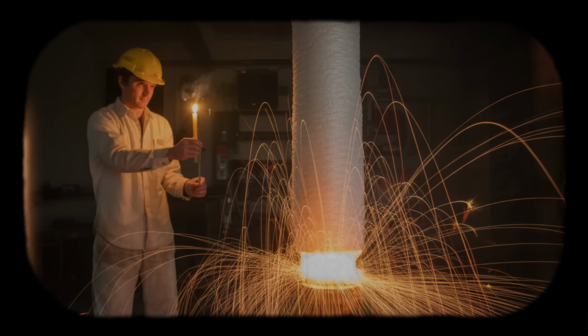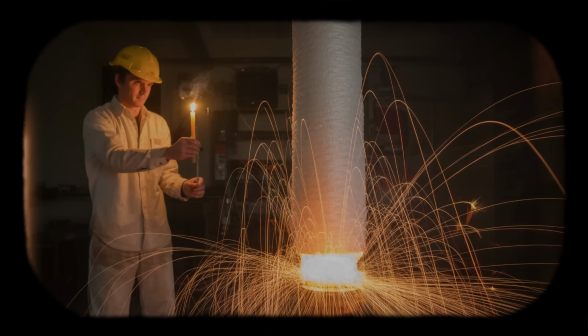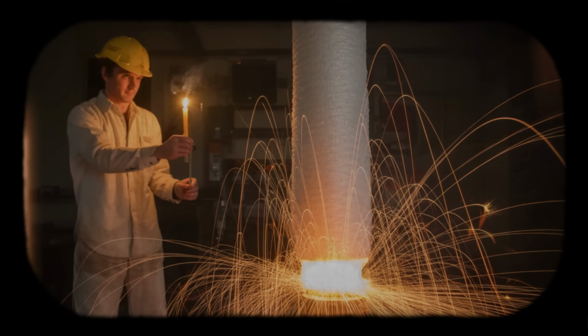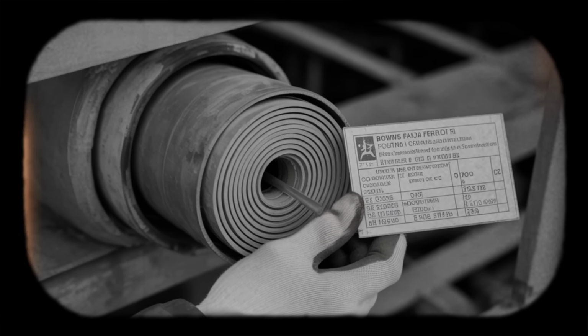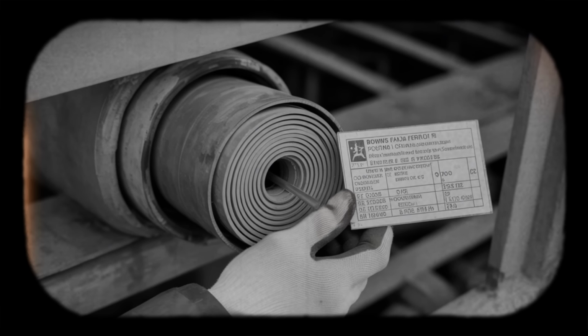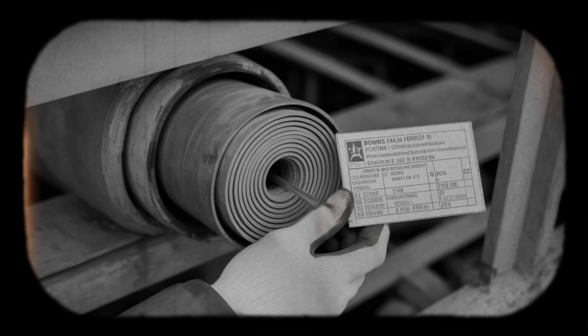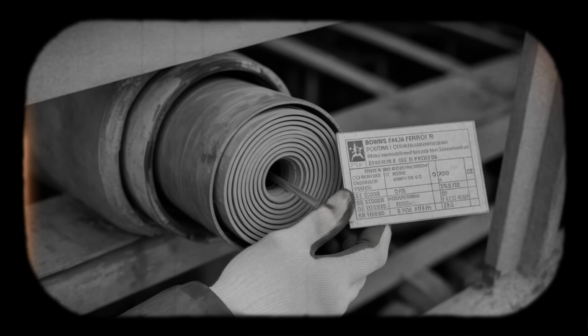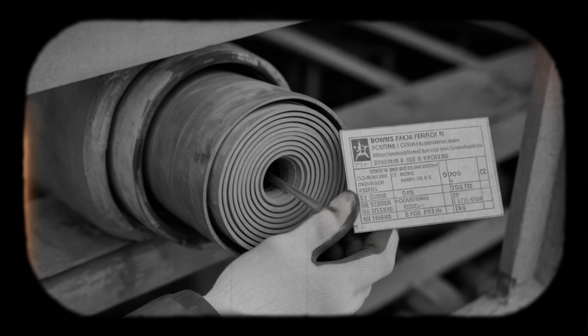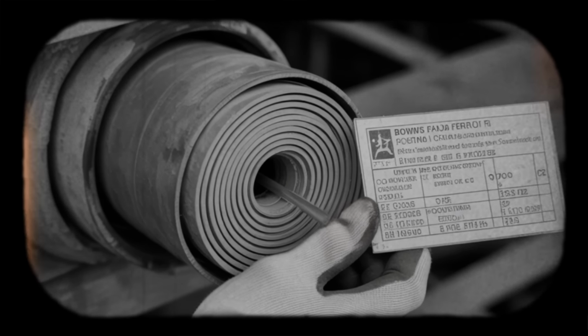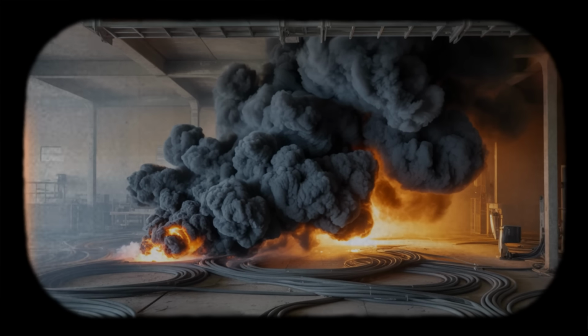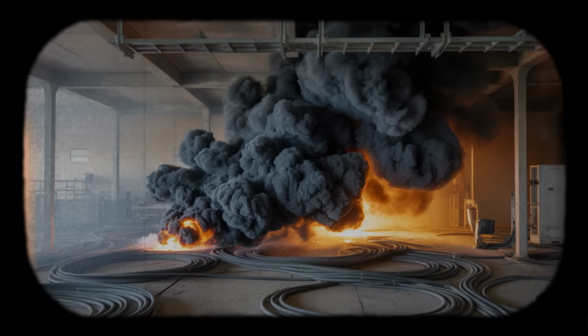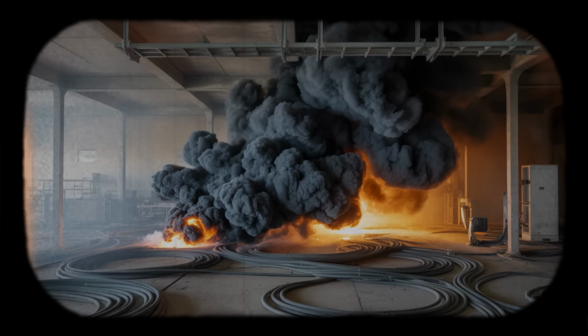As insulation burns, molten material drips onto cables below. Heat radiates to adjacent conductors. The fire spreads both upward towards ceiling trays and downward toward equipment rooms. Heat begins softening conductor sheathing throughout the affected section. When insulation melts, bare conductors come into contact with each other or with grounded metal surfaces. This causes electrical shorts, momentary or sustained current flows that should not exist. Shorts produce more heat. They also send false signals to control systems. A valve position indicator might show the valve moving when it is not. A pump status light might flicker on and off. Alarm circuits begin behaving unpredictably.